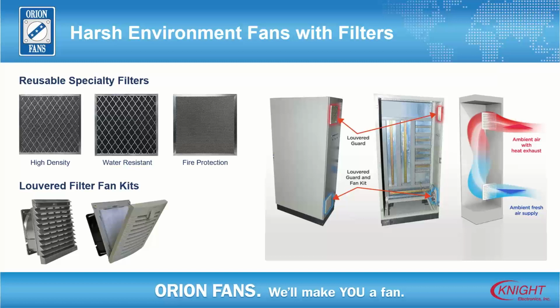So you take the styrene foam that's in there out, and you put one of these filters in there for various levels of protection. But everything you filter reduces your airflow. A standard louvered filter with just a standard filter in it is about a 40% drop in airflow just coming through the filter. That's pretty substantial. It varies a little bit from fan to fan and application to application. But that's a lot of airflow you're losing.